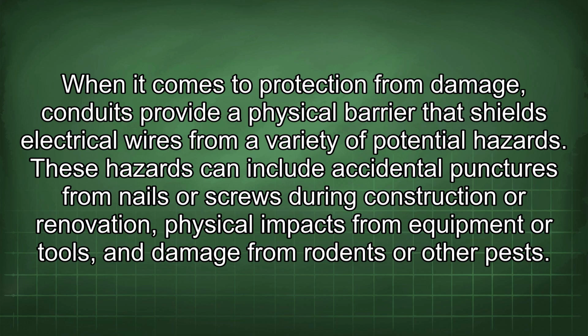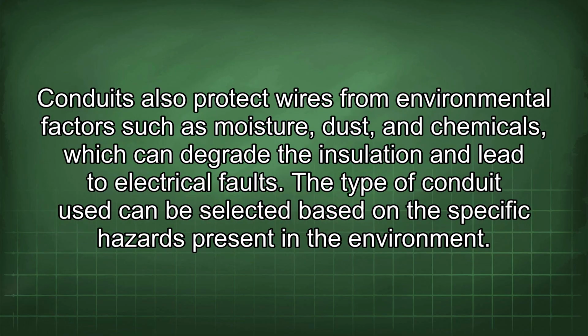When it comes to protection from damage, conduits provide a physical barrier that shields electrical wires from a variety of potential hazards. These hazards can include accidental punctures from nails or screws during construction or renovation, physical impacts from equipment or tools, and damage from rodents or other pests. Conduits also protect wires from environmental factors such as moisture, dust, and chemicals, which can degrade the insulation and lead to electrical faults.